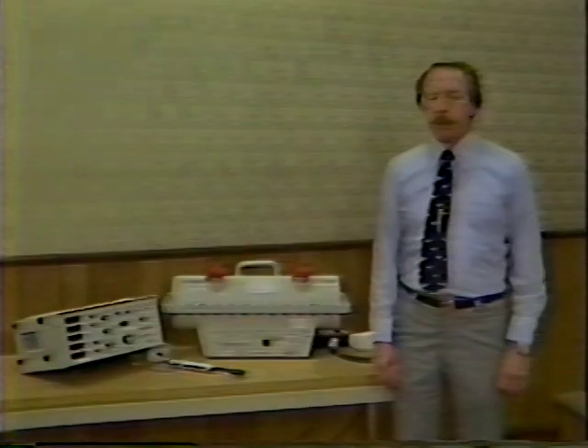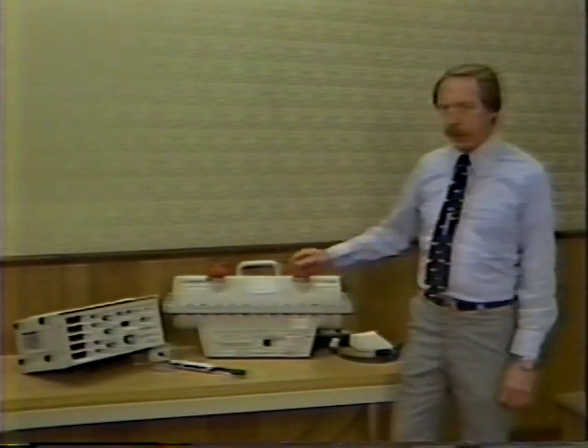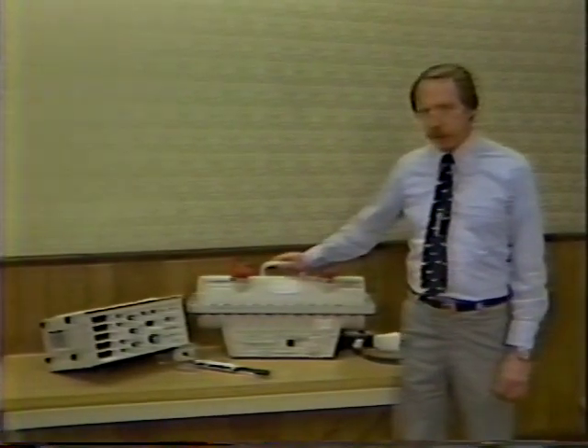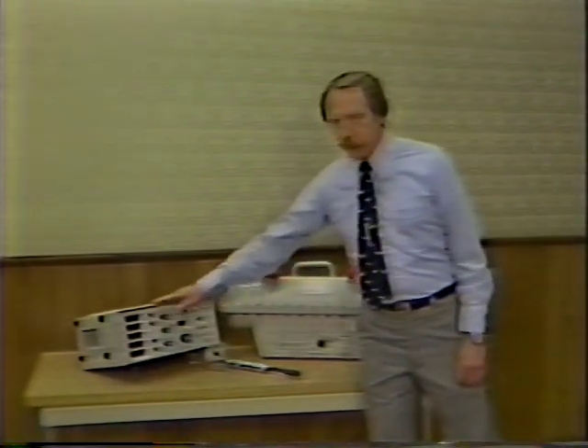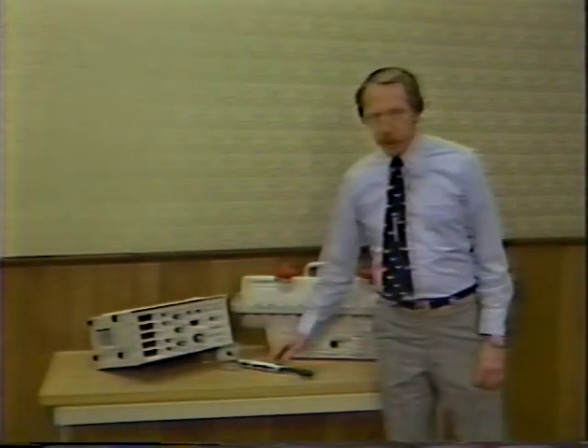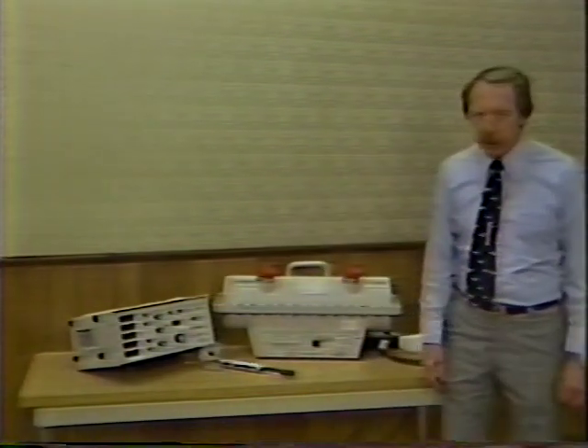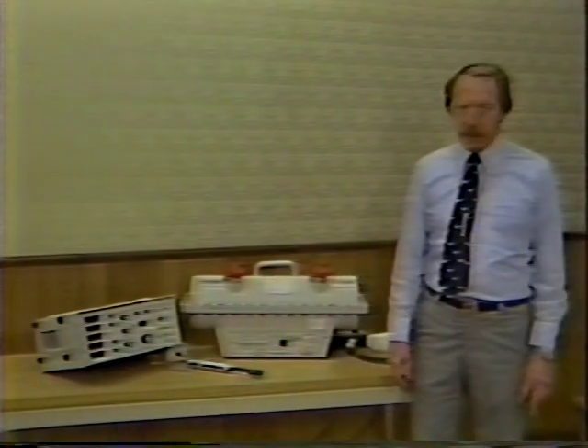The Dynalyzer 3 added the following capabilities: anode plus cathode KVP, MR per MAS, MR per second, coefficient of variation of 10 values, sliding sampling window for falling load generators, storage and recall of 10 exposures, printout of kiloheat units per exposure, printout of line voltage regulation, digital display of data, digital printout of data, with a weight of approximately 55 pounds. The Dynalyzer 3 system consists of 3 units: the high voltage unit, which is sometimes called the bleeder, the digital display with integral printer, and the radiation probe. Let's look at the specification on the Dynalyzer 3 system on the next slide.